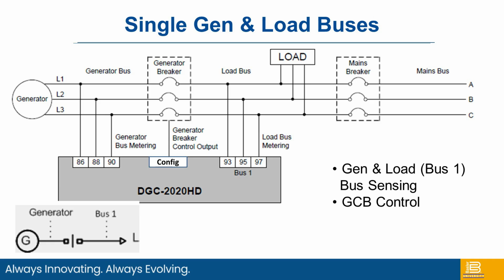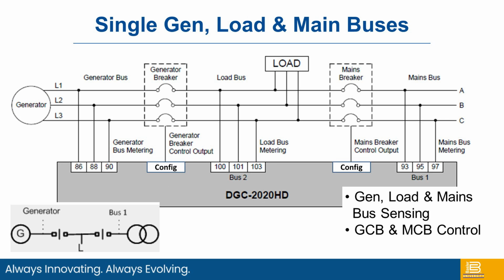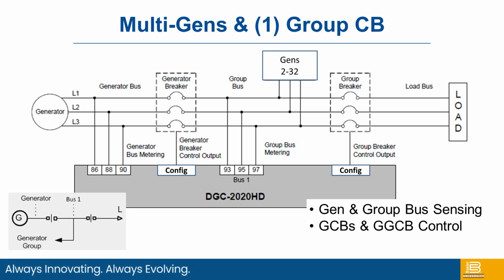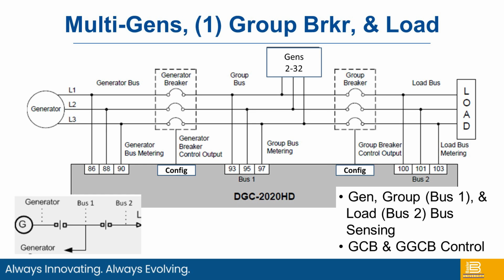So now we're controlling not only the generator circuit breaker, but we're also controlling the utility circuit breaker or the main circuit breaker. Gen, load and mains bus control, so GCB and MCB control as well. Then multiple gens. Again, as I stated earlier, we can parallel up to 32 gens together. This is an application where each one of the generators would parallel, as you see up in the upper side, gens 2 through 32. They would parallel to the bus and then a group breaker. We can also do multiple gens, one group breaker and the load breaker.